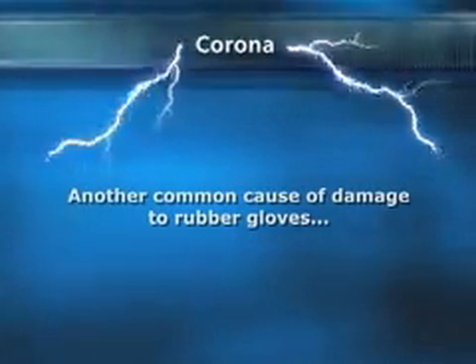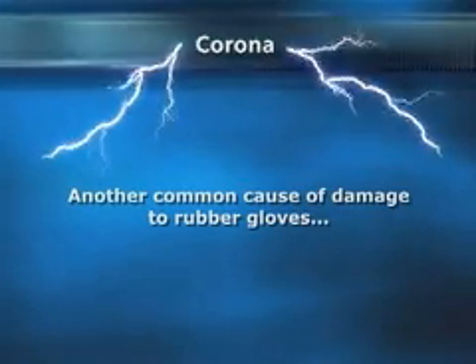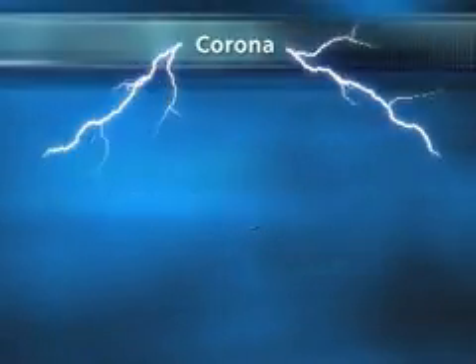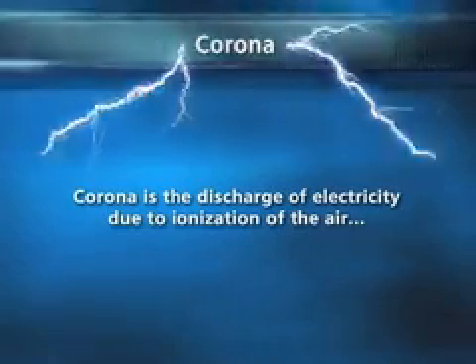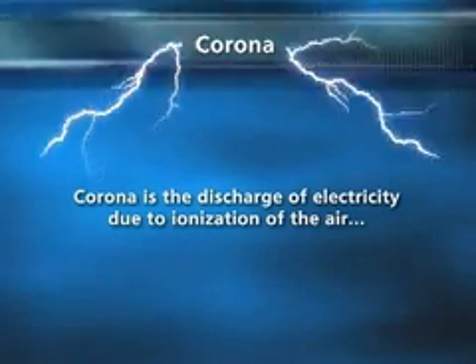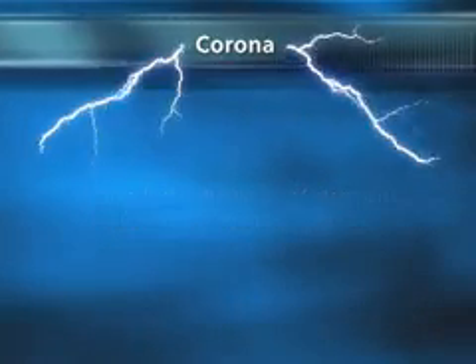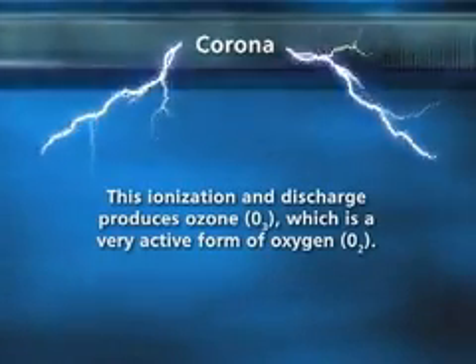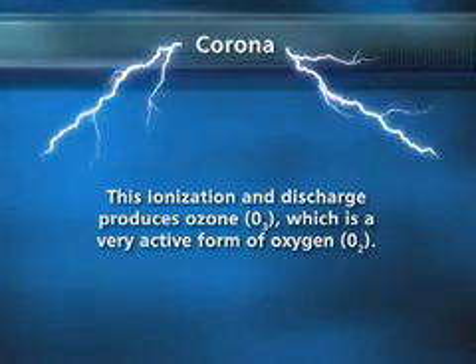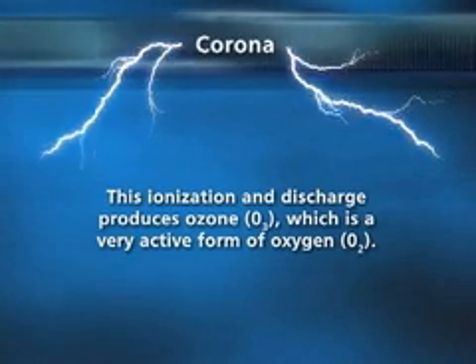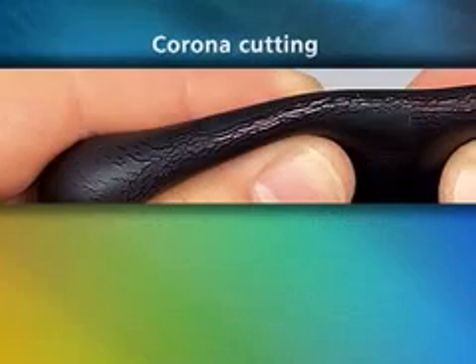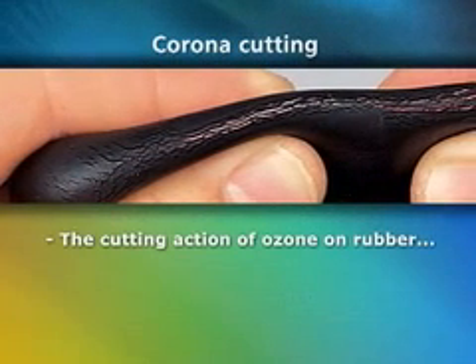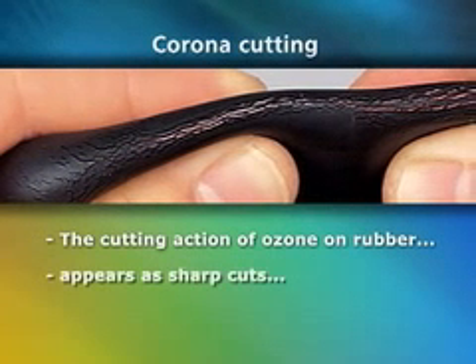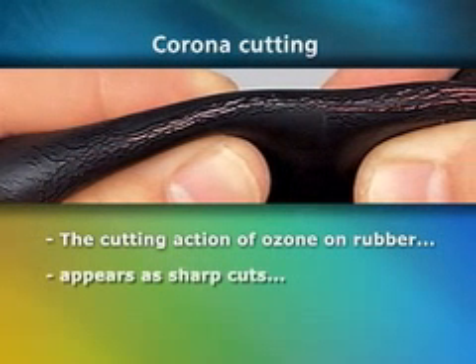Another common cause of damage to rubber gloves is corona, or ozone cutting. Corona is the discharge of electricity due to ionization of the air surrounding a conductor under high voltage. This ionization and discharge produces ozone, which is a very active form of oxygen.